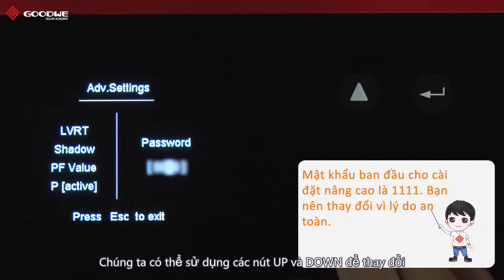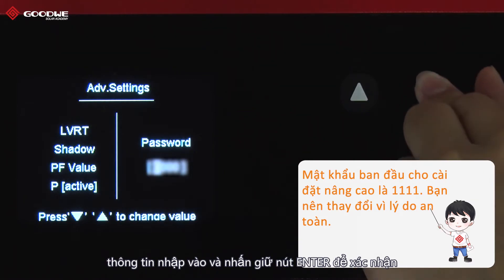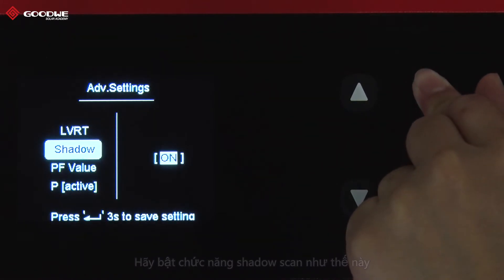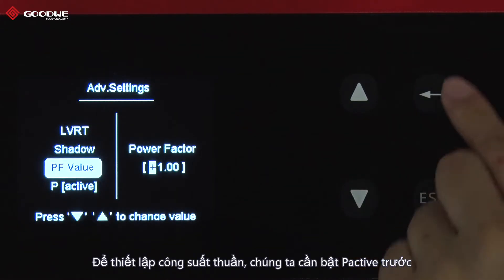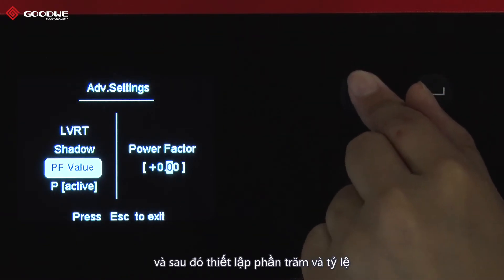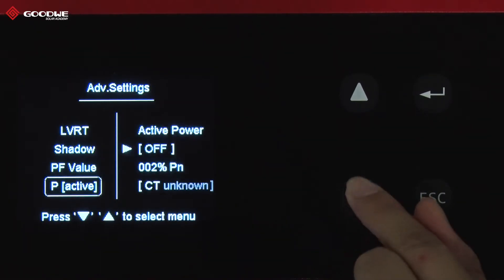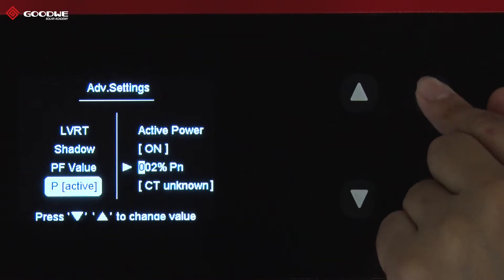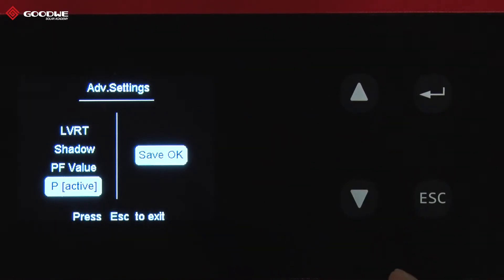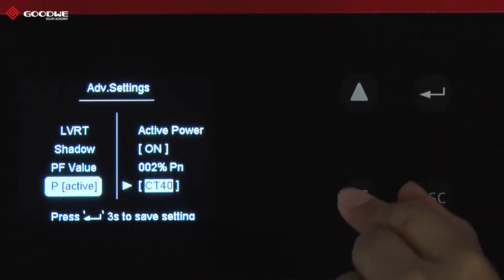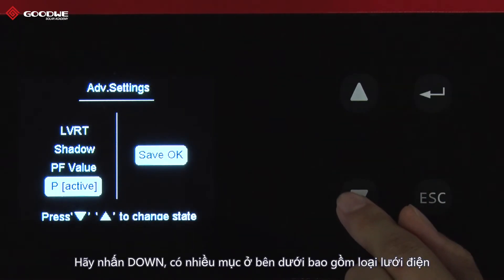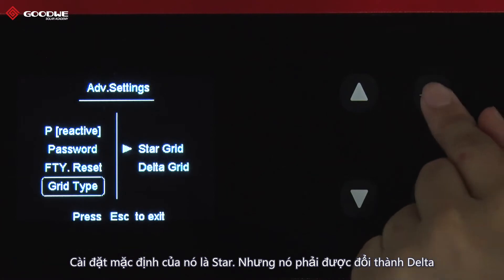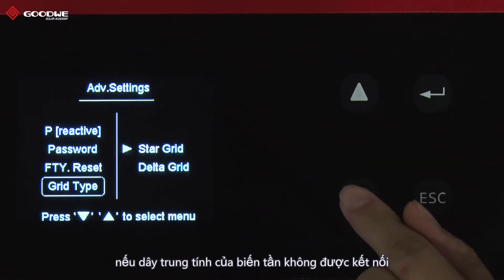We can use the Up and Down buttons to change the inputs and long-press Enter to confirm. Now we can start advanced settings. Let's turn on the shadow scan function. To set active power, we need to turn on P-active first, and then set the percentage and ratio. Press Down — there are more items including grid type. Its default setting is star, but it has to be changed to delta if the neutral wire of the inverter is not connected.